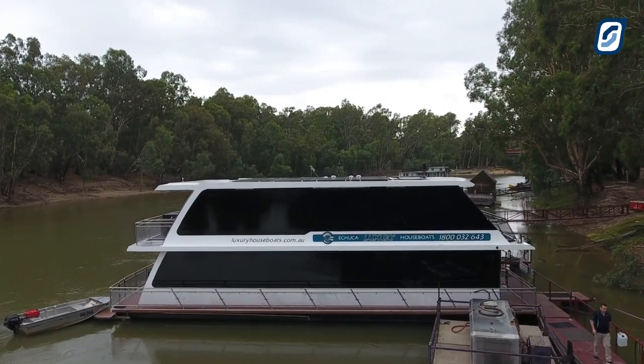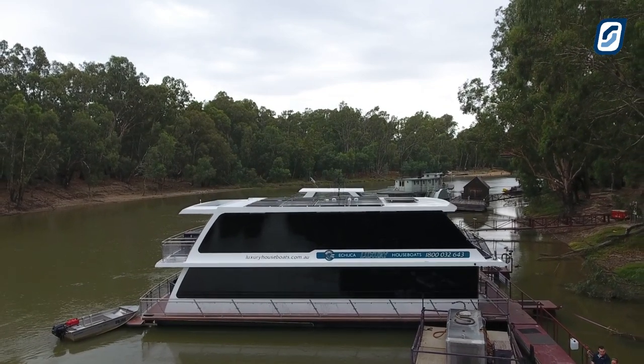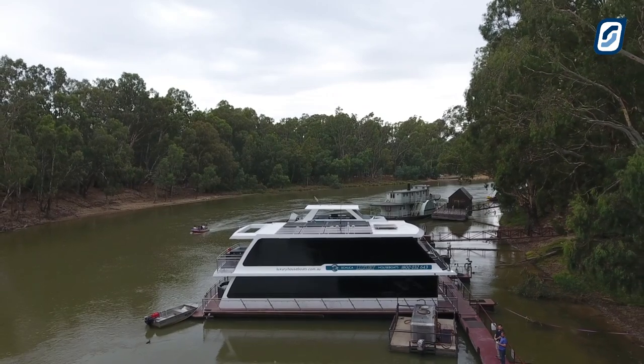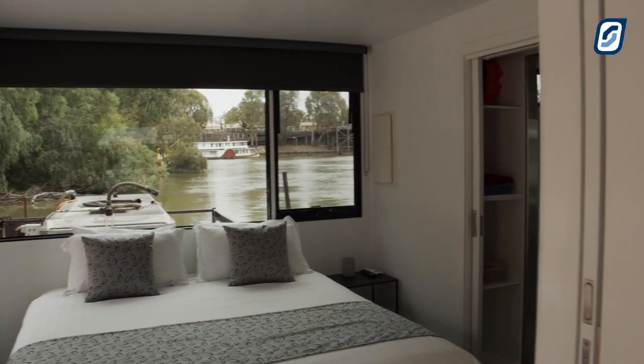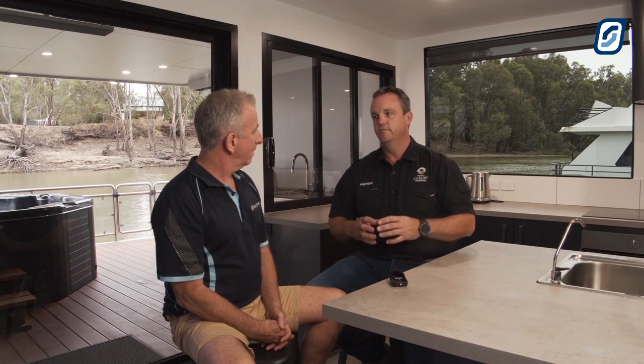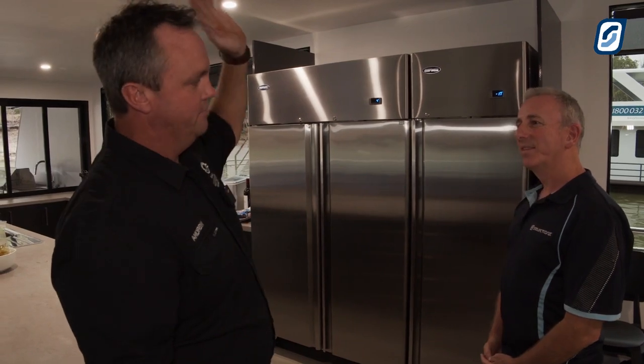So what was this particular project? This boat is called Absolute. What's the thinking behind the project? It will speak for itself. We've got five bedrooms with en-suites on board, and reverse cycle heating and cooling into the bedrooms. One of the main goals we wanted to achieve with our electrical system was to be able to run the reverse cycle into the bedrooms overnight, plus the fridges and other loads on board, without having the generator starting. With this new parallel inverter-based system, we're achieving that — we're seeing absolutely whopping loads, around 100 to 120 kilowatt hours per day.